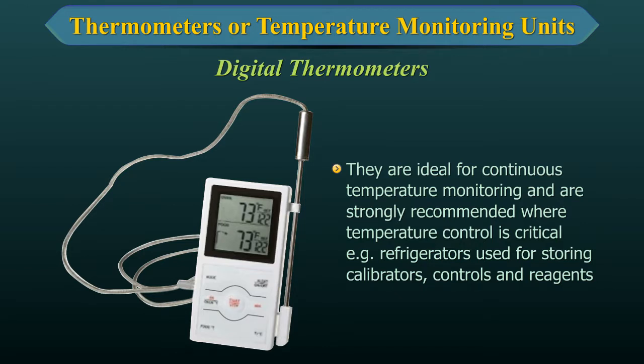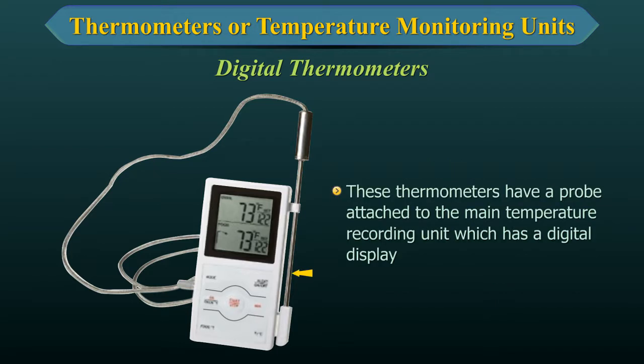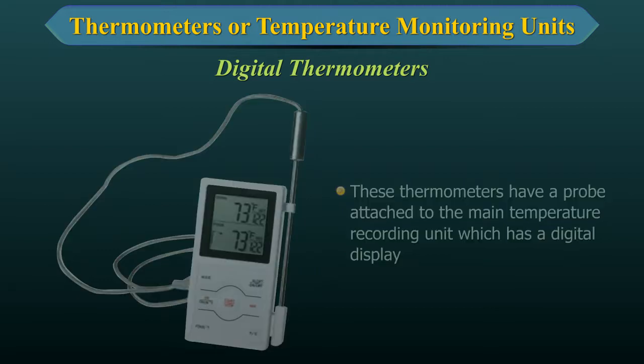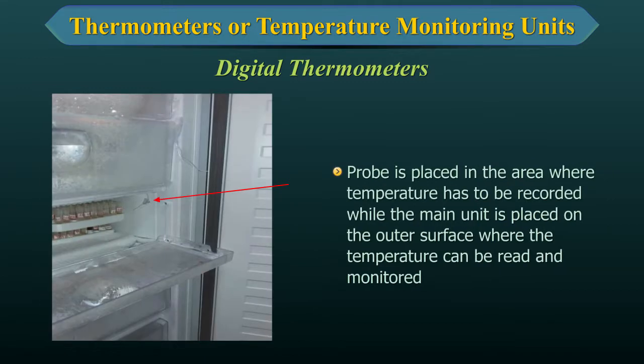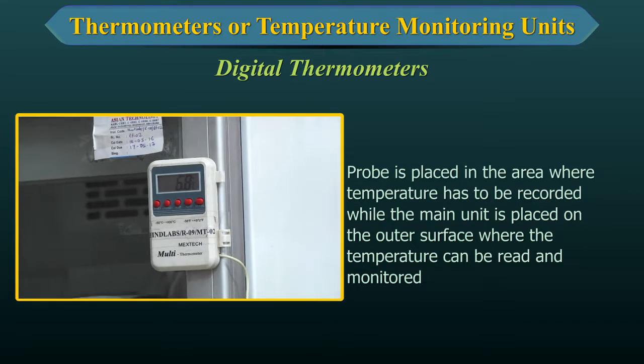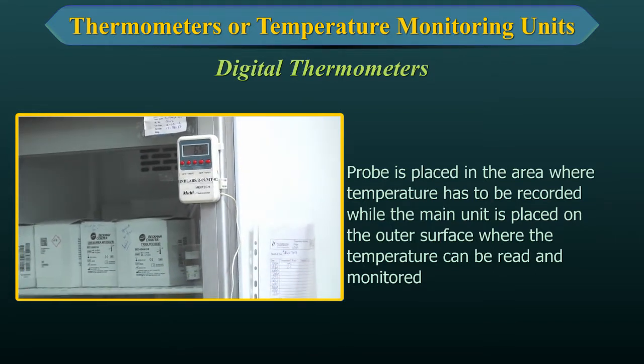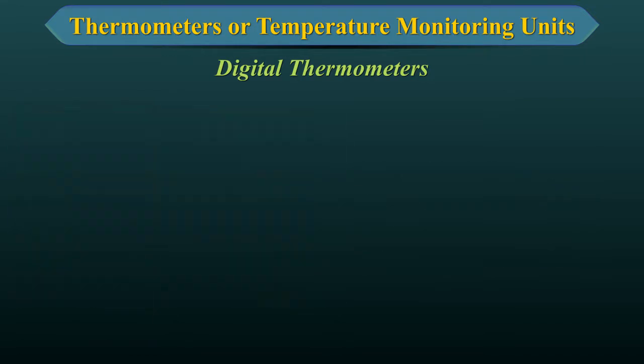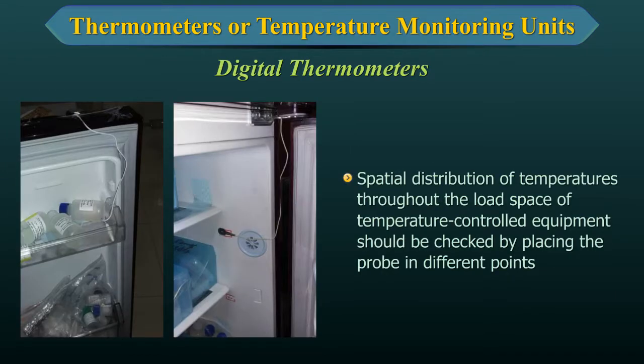Digital Thermometers. They are ideal for continuous temperature monitoring and are strongly recommended where temperature control is critical. These thermometers have a probe attached to the main temperature recording unit, which has a digital display. The probe is placed in the area where temperature has to be recorded, while the main unit is placed on the outer surface where the temperature can be read and monitored. The spatial distribution of temperatures throughout the load space of temperature-controlled equipment should be checked by placing the probe in different points.